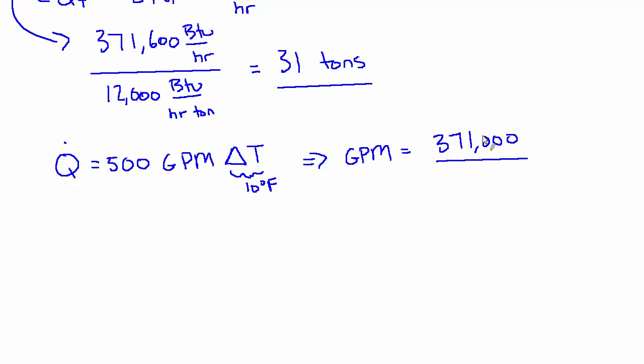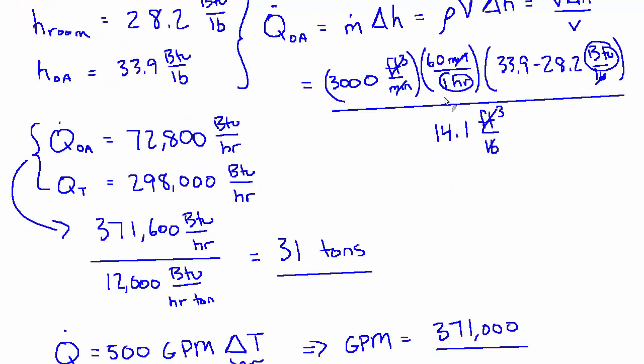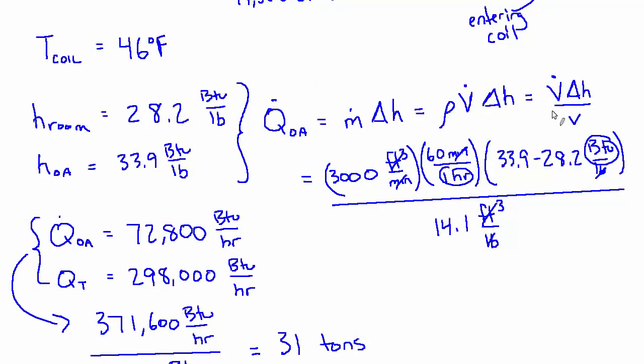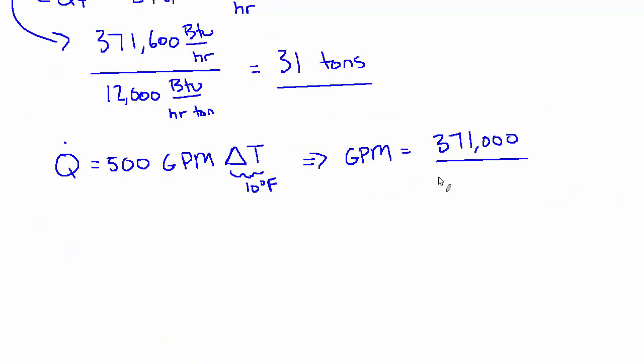That's why I don't bother to write the units when I make the substitutions, even though I'm a stickler about writing units, like what we did up here, where we're adapting a formula and then making substitutions based on something we came up with on the spot. So 371,000 over 500, and the delta T is 10. So that's 74.3 GPM.